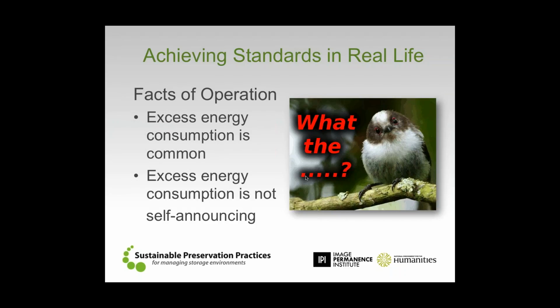More often than not, what we run into is that the environment, in the end, the temperature and the relative humidity in the space look exactly like what the institution expects, exactly what people are looking for. But it's in the background, it's the details of how the air is worked on, of what each component is doing and performing, that really lead you to find out and go, wait a minute, we're not doing this as efficiently as we could, or we're wasting energy in this particular operation that is unnecessary at the end of the day when we're looking at the preservation goal.